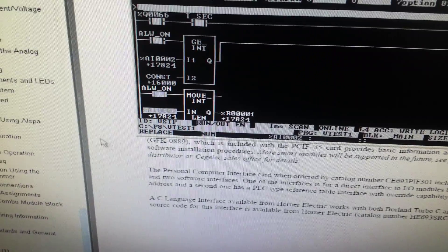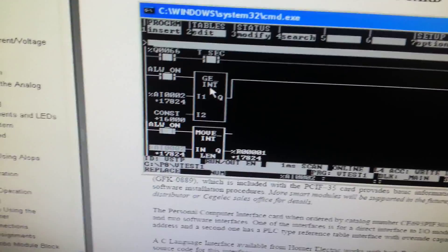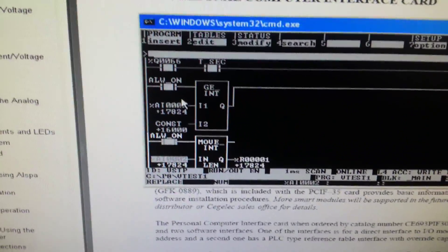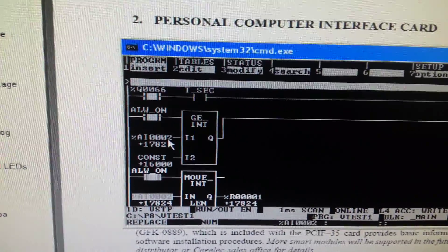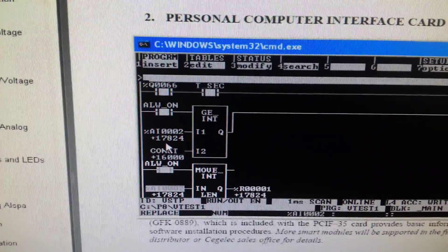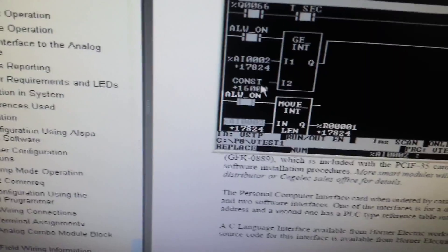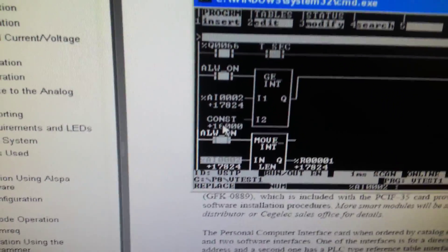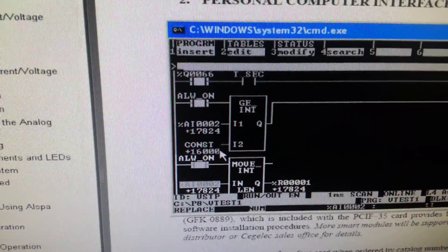I created a simple logic block — a greater-than-or-equal-to block in integer format, GE underscore integer. The analog input AI 002 is the second input from our analog input card. The current value now is 17,824, which corresponds to 12.92 milliamps.